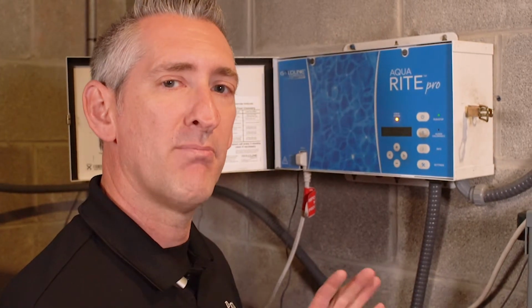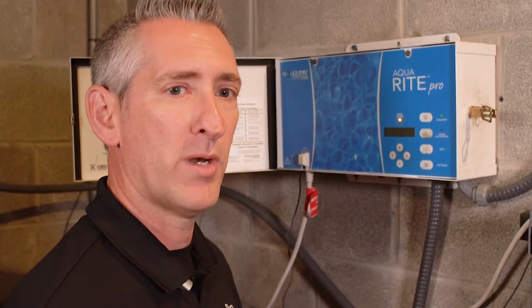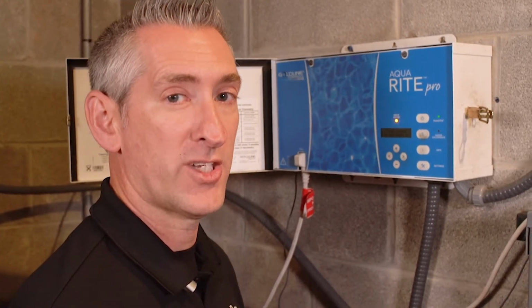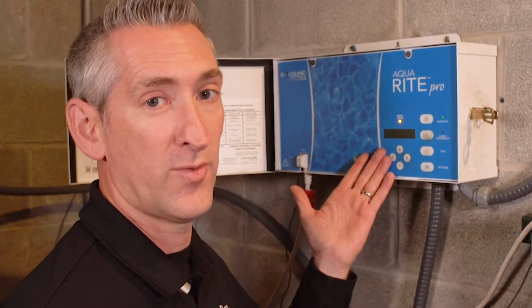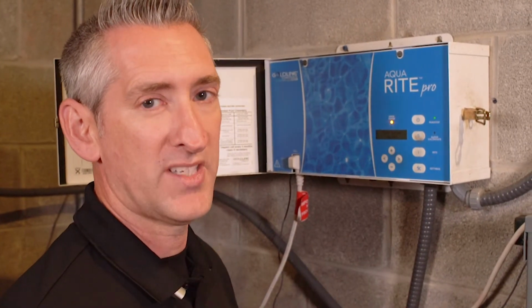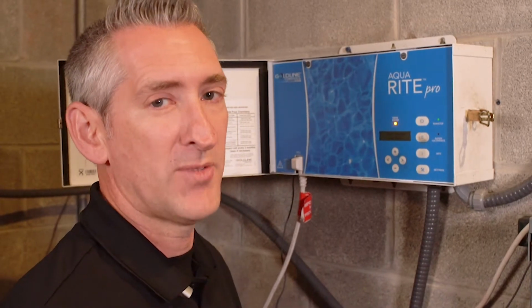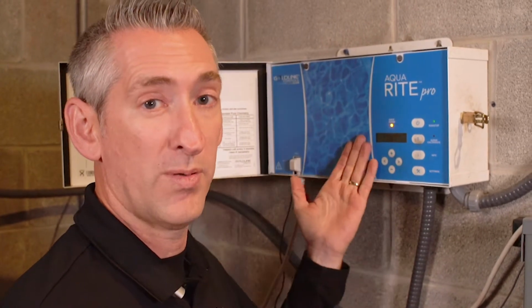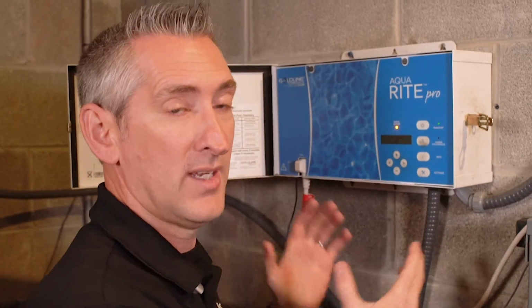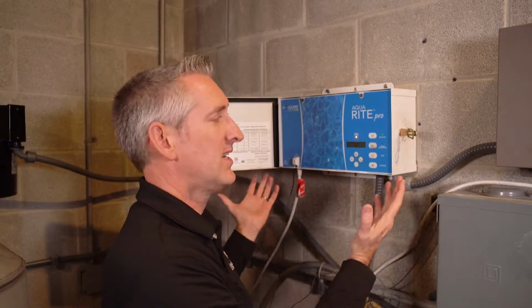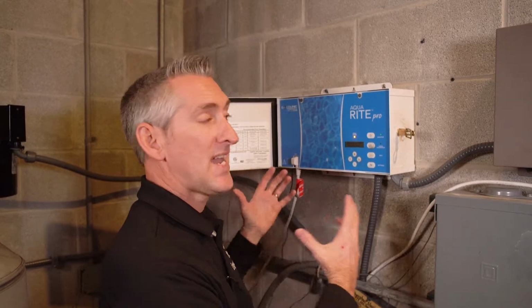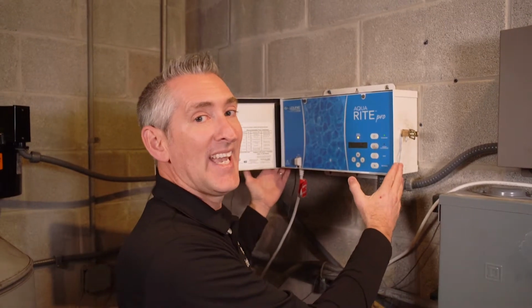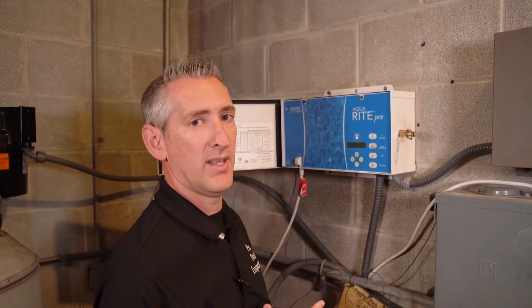So if you recommend to the customer that it be repaired, you cannot buy the manufacturer repair motherboard by just soldering it. They recommend they be replaced. So we always recommend to our customers that if they don't have any readouts going on the readout screen, that they replace the motherboard inside the unit. And that's going to be up to you whether or not you make that determination of whether to replace the board or to replace the whole unit. So you can tell by the signs of this one, it's still in good shape because it's indoor. You may have some where the cabinets are rusty. In those indications, we do recommend that the customer replace the whole unit because it's probably time.